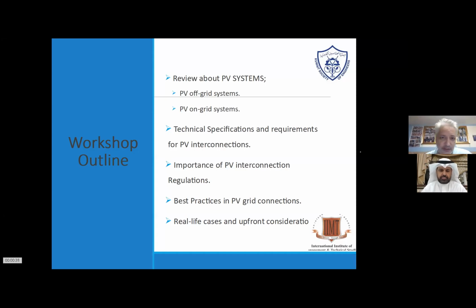So when we troubleshoot existing systems, we're looking at off-grid and on-grid systems, and nowadays also hybrid systems. So we need to know mostly the included materials, the technical specification, the requirements, and the interconnection rules in each different country, as well as the different setups according to the inverter manufacturers. We can see that sometimes a German grid setting is used, or Italian, or English, for countries that are new to PV systems. Mostly after 1-2 years, these settings will be fine-tuned to the settings of the country. So therefore we sometimes encounter problems in the beginning, but this can be fine-tuned, as said, by the different people involved.